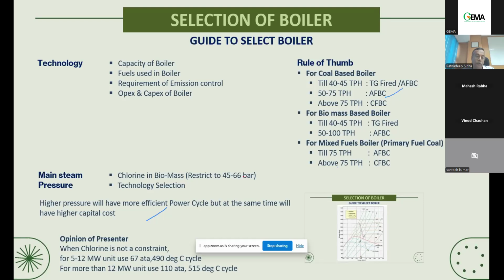So when chlorine is not a constraint, for a 5 to 12 megawatt unit, the optimum pressure and temperature is 67 bar, 490 degrees, and if it is more than 12 megawatt, say up to 20-25 megawatt, or maybe up to 30 megawatt also, 110 bar at 515 degrees centigrade is the recommended pressure and temperature.